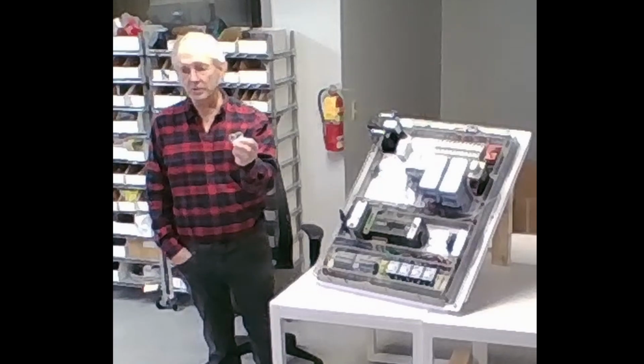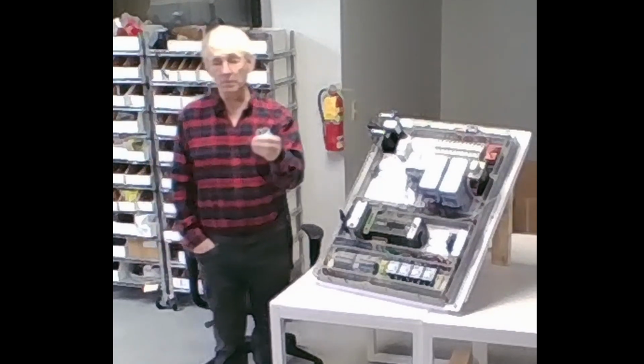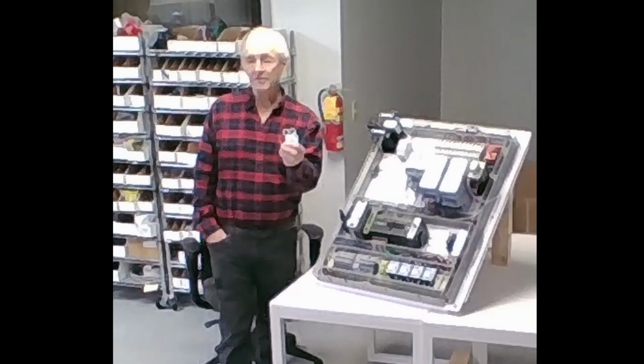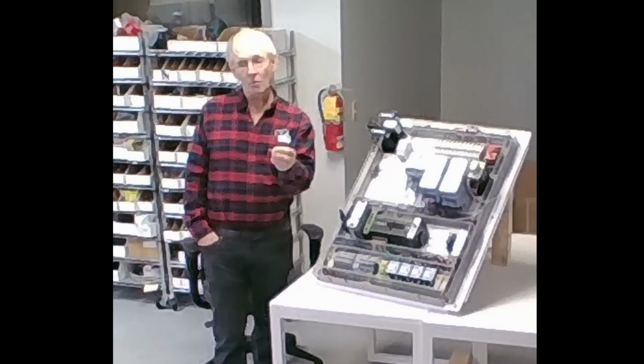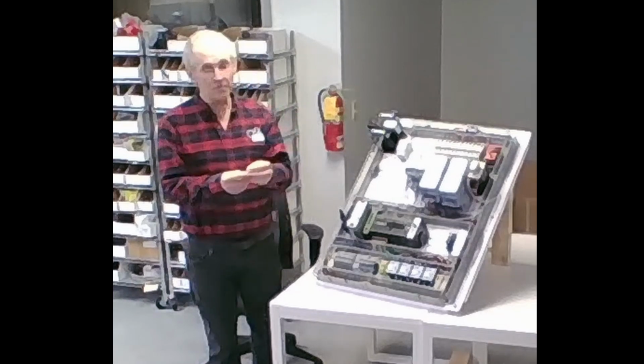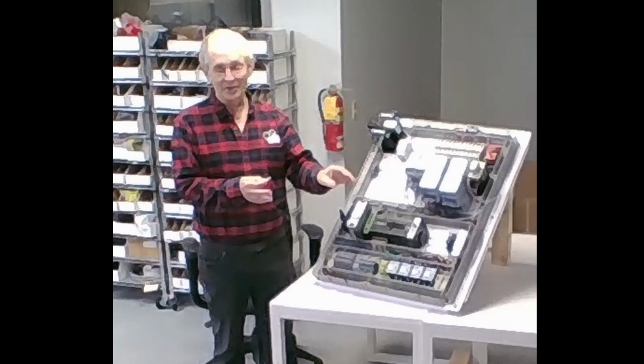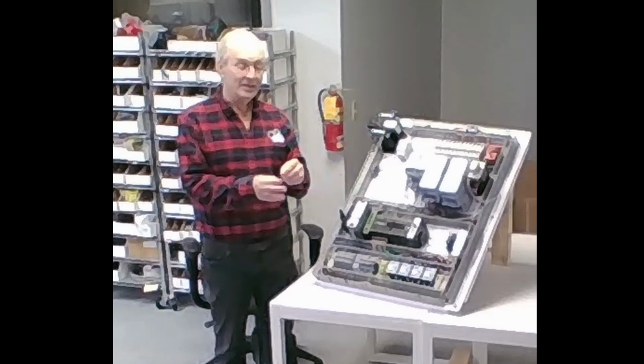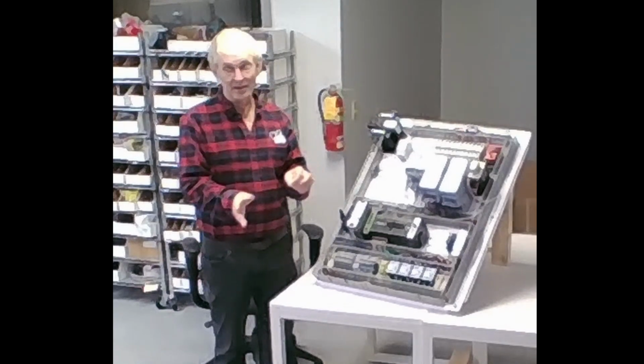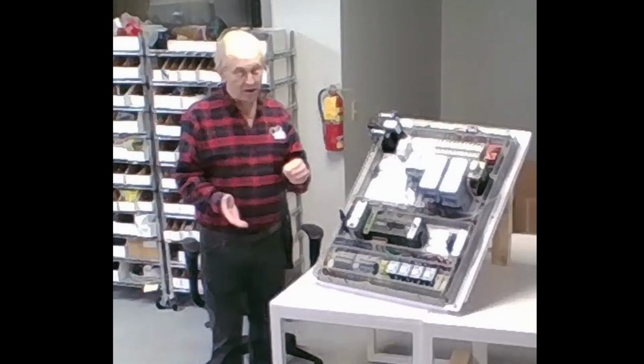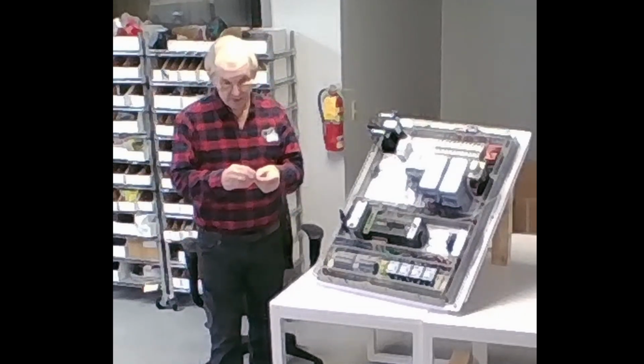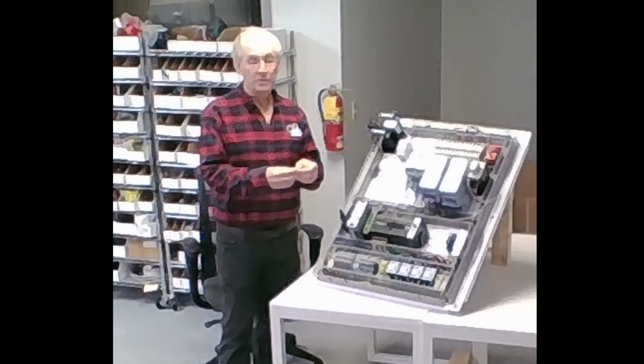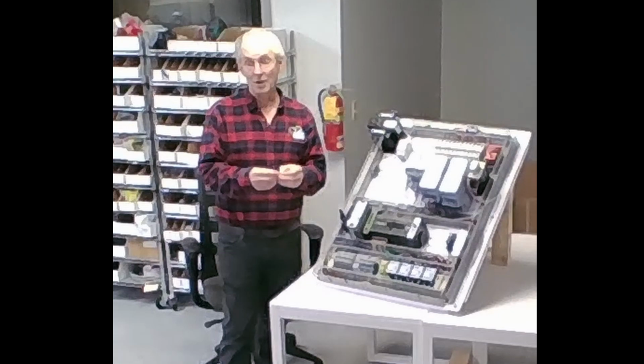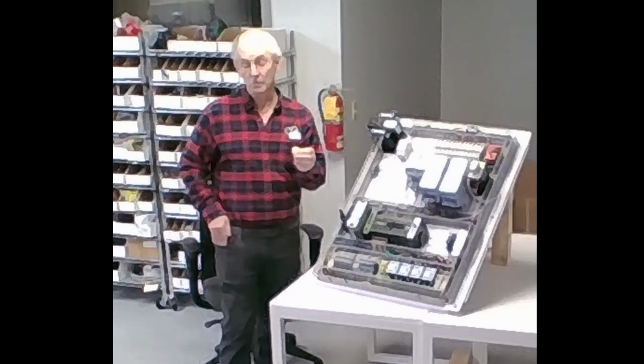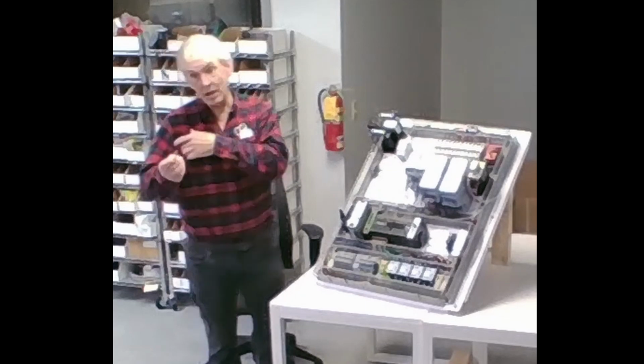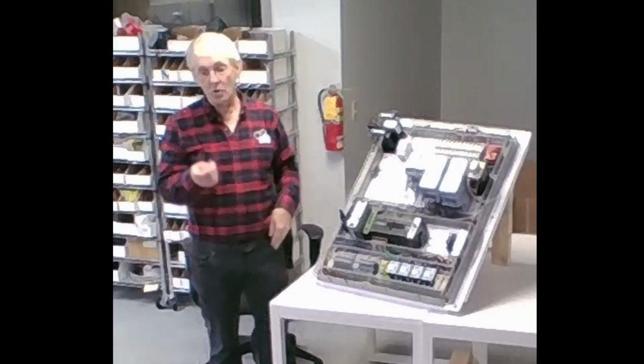And so you can tell just by that what kind of problem you're looking for when you find a bad fuse. If I see it melted out, I'm not going to find a wire. If I see where it's just gone, I'm not going to find some place where it arced. That's like the equipment that it's feeding went bad and is pulling too much current. Now, if I see it all blackened, I'm going to go looking for a pinched wire or that kind of problem. I'm looking for something that was a short to ground or to the other side and caused it to flash.